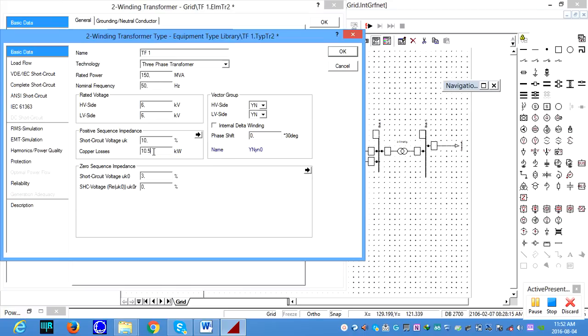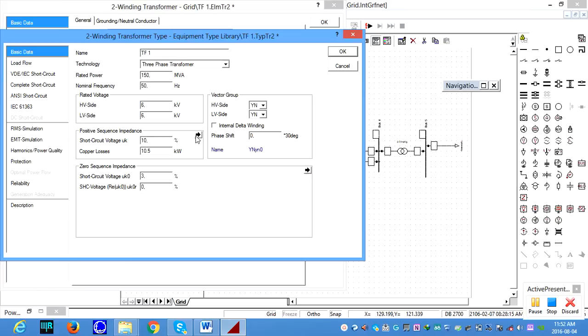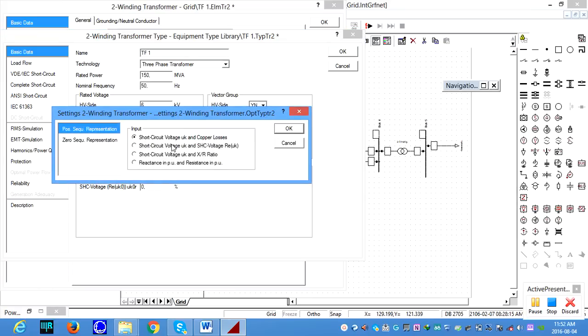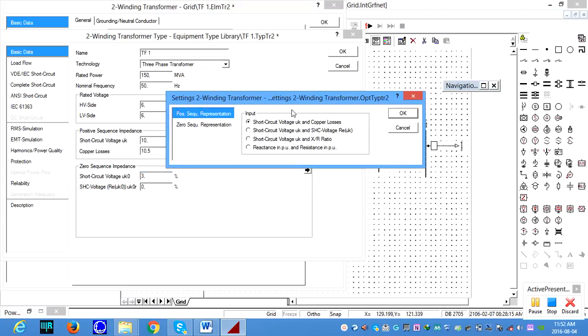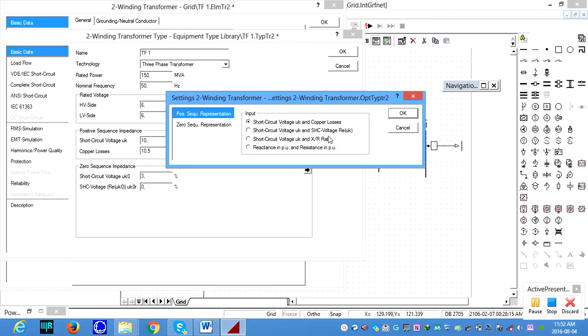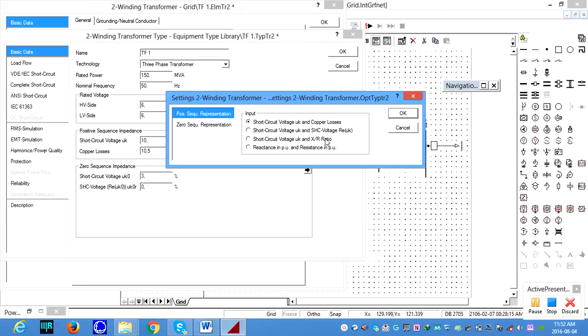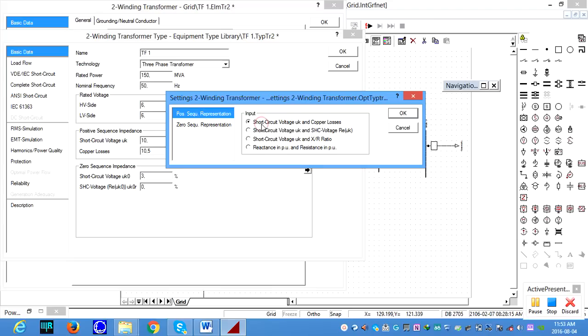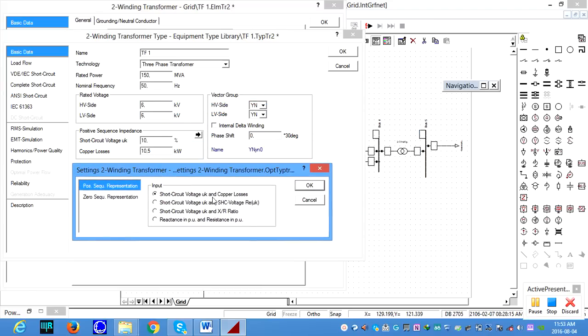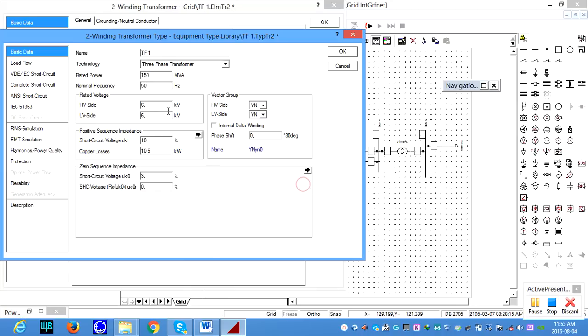5 kilovolt. Okay. And underneath that, you can see it's a positive sequence diagram. These options, if you select, either you can give the short circuit voltage and copper losses, otherwise you can give the short circuit voltage and the short circuit voltage UK, and maybe you can also have options to select the short circuit voltage and the XR ratios, or maybe the reactance and resistance in per unit. But in this case, the transformer data is given as short circuit and copper losses, so we are happy about that. And the transformer is a three-phase transformer.